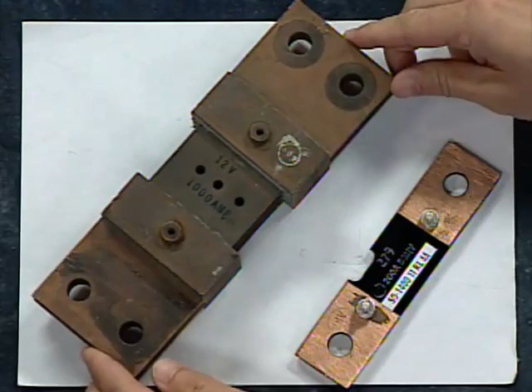So here's a beautiful one, and I haven't run the amperes through it myself yet, but I will. Lead acid batteries. Yes sir, and I see the rating is printed on here: 12 volts full scale at 1,000 amps. It's not good for 120 volts. Not that it wouldn't survive, but it's not a great idea. Is that the shunt rating, or the millivolt circuit rating?